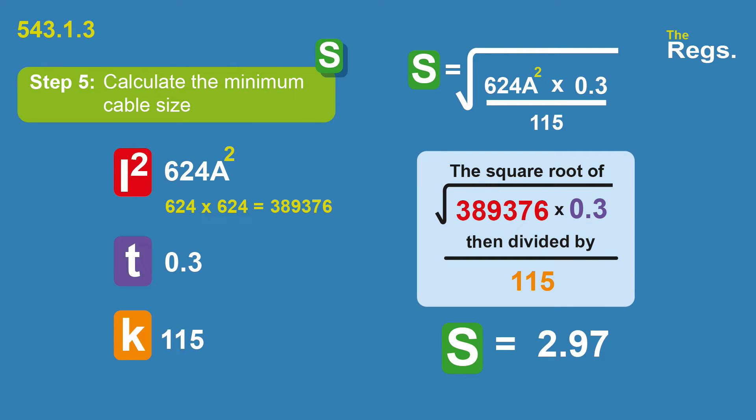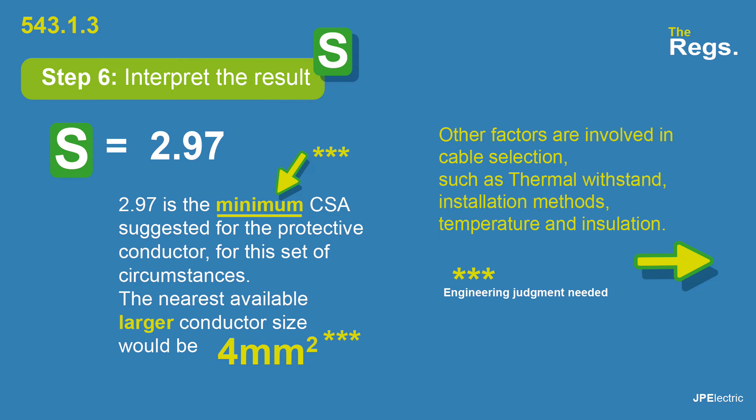We've got all the numbers we need: fault current, time, and K value. So the sum is the square root of 624 squared times 0.3, then divide that total by 115. We don't square root the whole sum — just square root the top line, then divide by 115. That gives us a minimum cable size of 2.97 millimetres squared. So the nearest available larger conductor size would be 4 millimetres squared — you have to go larger, as 2.97 is the absolute minimum.